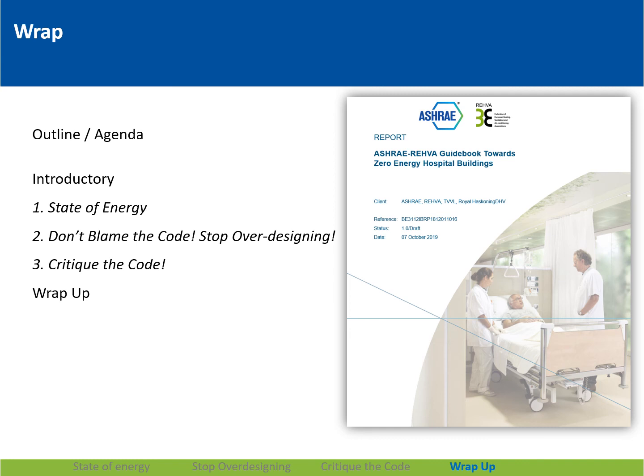So to sum up my message, most of the energy we waste in hospital HVAC is really not code related. It's related to our design and our validation practices. So as design engineers, we need to stop blaming the code, take responsibility for what we can, and start doing a whole lot better with what we can. And second, critique the code. I think it's perfectly fine to critique the code. To many of our designers, we treat these things like they're sacred, but really it is an ASHRAE standard. And if you're a member of ASHRAE, that means it's your standard as much as anyone else. In the long run, I think we need to be accountable and responsible for making sure that the numbers that we have in our code are quality.